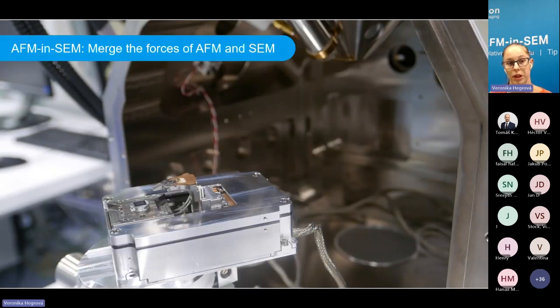So let's start with the AFM in SEM, how it actually looks like. If you have a look here, we have the LiteScope, a unique atomic force microscope, which fits into almost any SEM chamber. And so we have LiteScope sitting on the stage. And over here, you see the SEM chamber and the objective over here. So there are just two cables which need to be connected, and we install this procedure each time before the measurement, so we don't occupy the chamber when not needed.